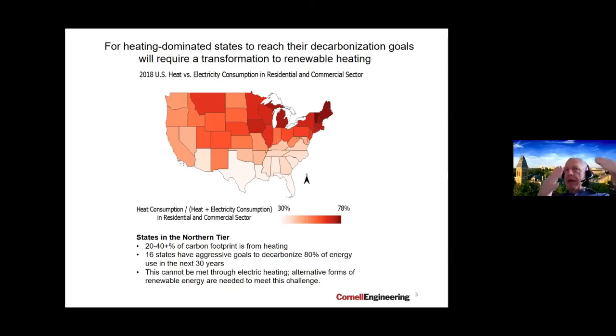The advantage of that type of cycle over the steam cycle is that they re-inject all of the fluid back into the ground and have no emissions at all - no carbon dioxide, nothing else to deal with. Whereas a steam system has possible disadvantages in that it will have some dissolved gases in the water as it's produced, which get separated, and that contains some CO2 - small amounts compared to burning fossil fuels, but still an issue. That's one reason why organic Rankine cycles, completely closed on the geothermal side, are becoming more attractive.